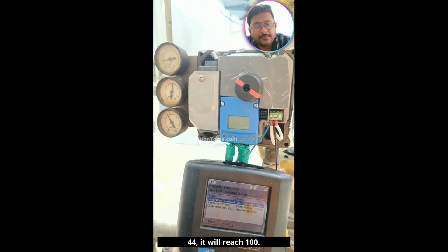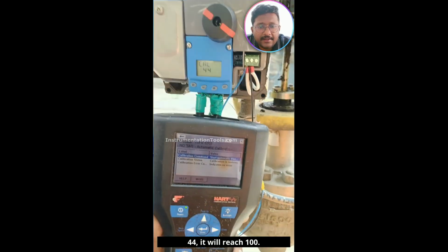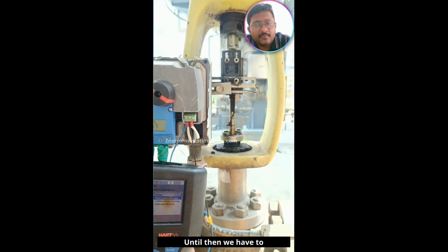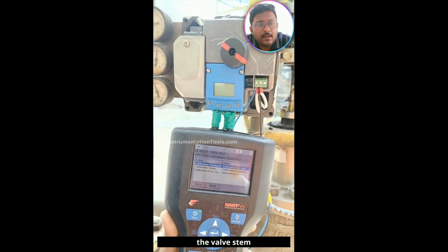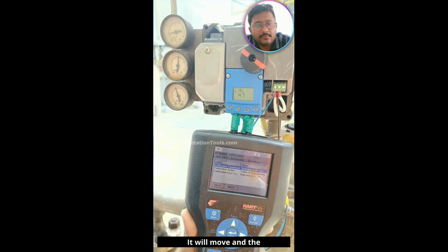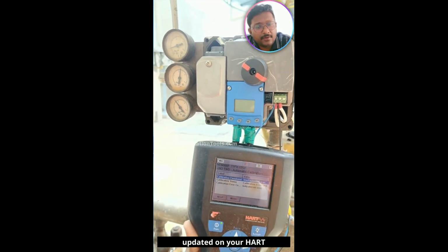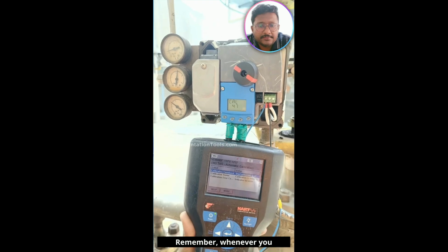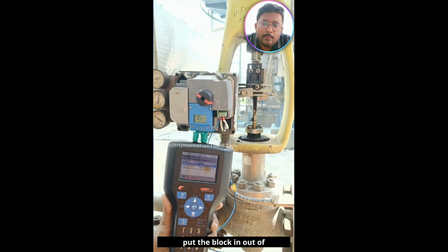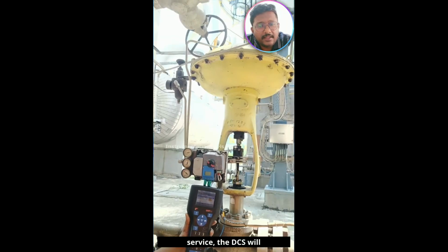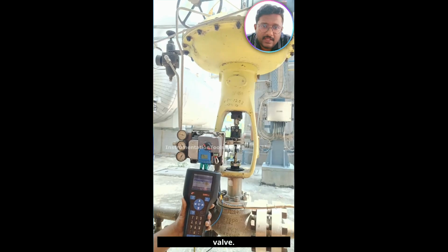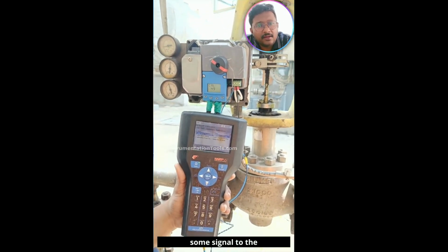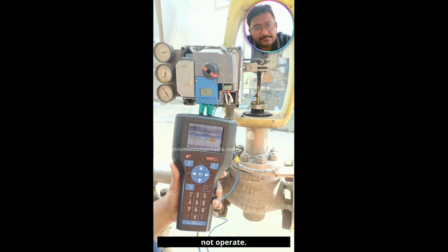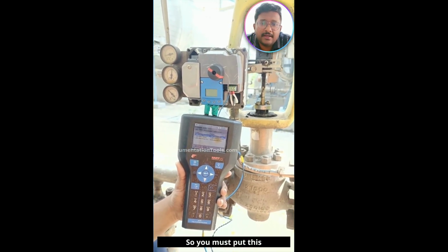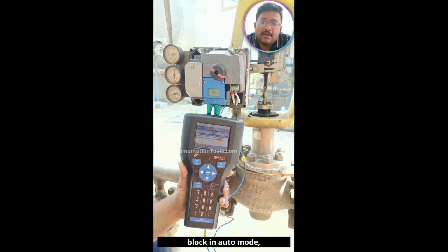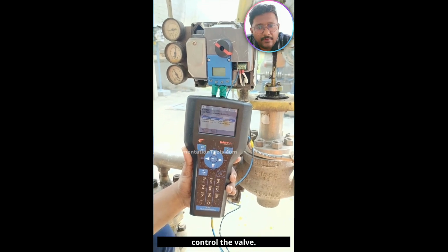Right now, the status is 44. It will reach 100. Until then, we have to wait. Meanwhile, you can see the valve stem position also. It will move, and the status also will be updated on your HART communicator. Remember, whenever you put the block in out of service, the DCS will not control this valve. Even if the DCS gives some signal to the control valve, it will not operate. So you must put this block in auto mode, then only the DCS can control the valve.